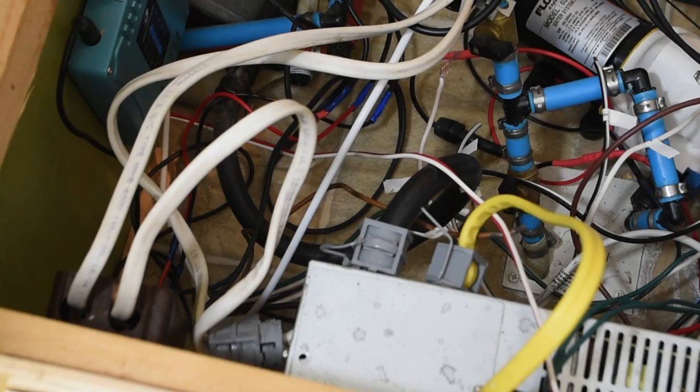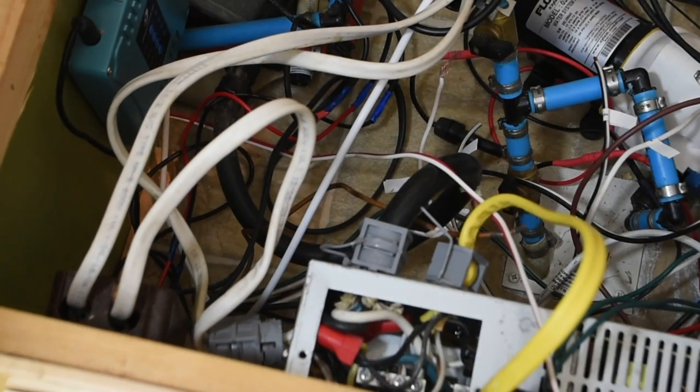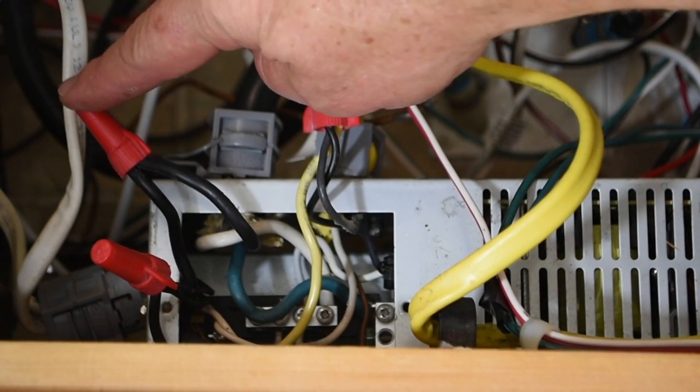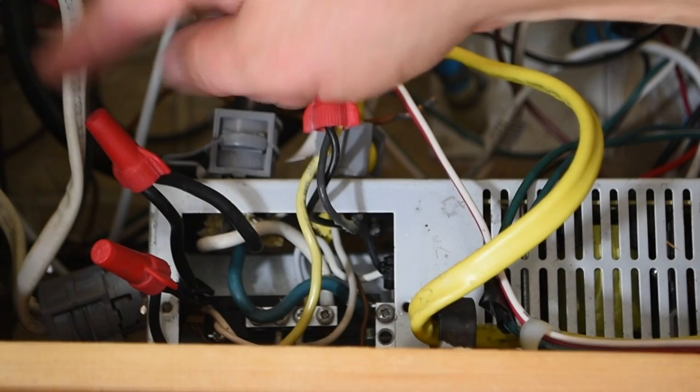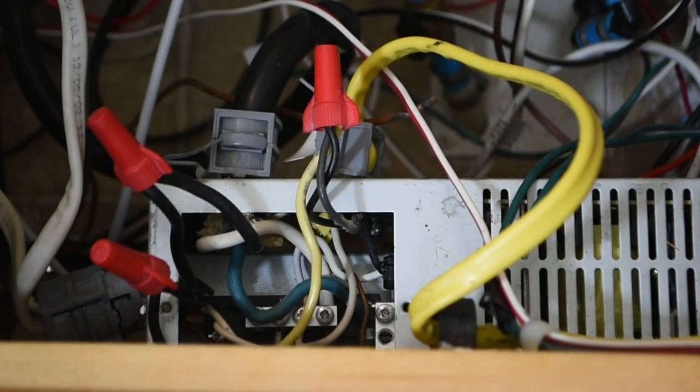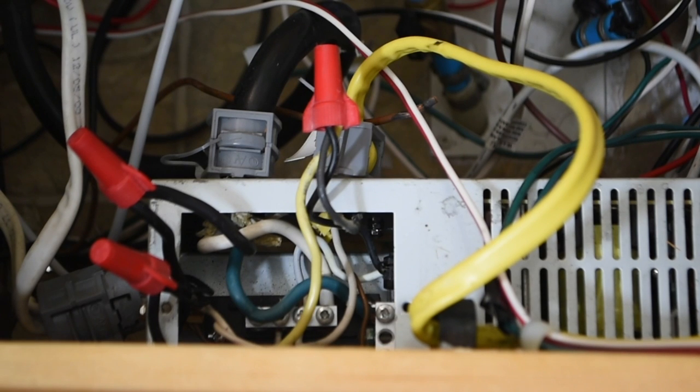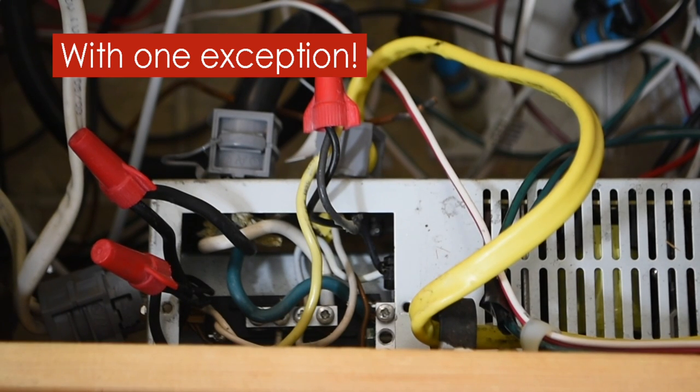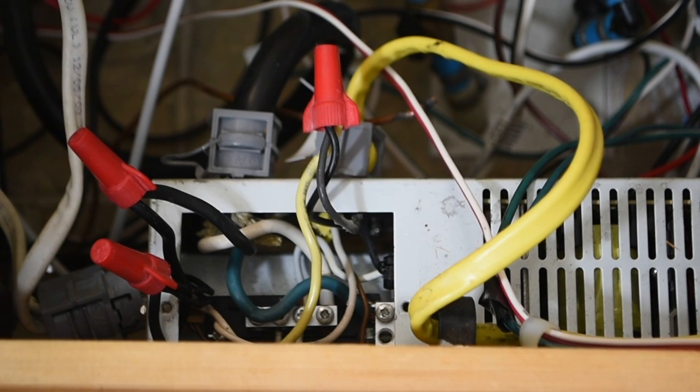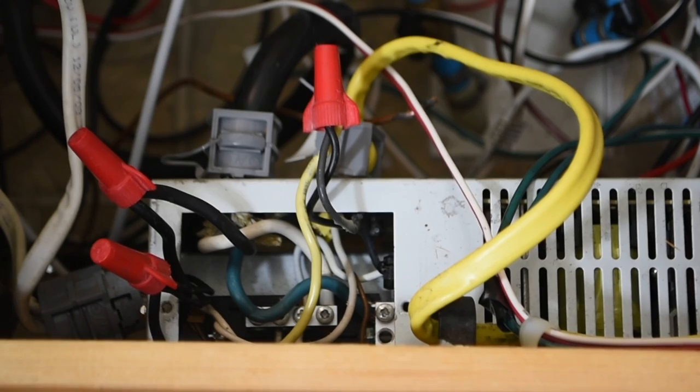Something else I wanted to point out real quick, as you notice that there's two colors of Romex in here. There's this yellow Romex, this is rated at 20 amps, it's a 12 gauge wire. And this white Romex is rated at 15 amps, it's a 14 gauge wire. So that also helped me identify which was running to the AC air conditioner and what was running to the outlets, as well as it'll help me map out what circuit breakers to use.